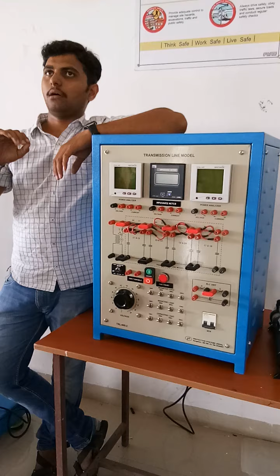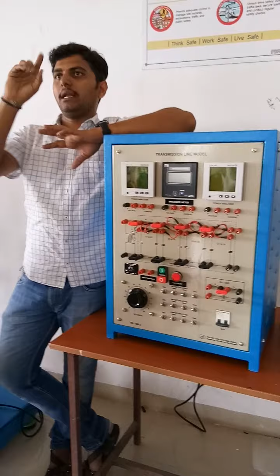A short circuit. And in SIL, surge impedance loading, what exactly happens is the voltage, the power rating will be rising up to the mark, and again it dips. So you have to note the peak value. That is the surge impedance loading value, that is the square root of L by C. That is the peak voltage, the peak load that the transmission line can withstand. After that, again the efficiency decreases. At the peak value, it gives maximum efficiency. So only we perform the SIL, surge impedance loading.